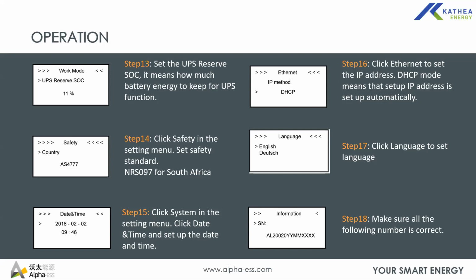On basic, you can set your language. It comes with two languages, which are English and German. It usually comes with default English, so if you feel like you want to use German, you can select German. And then there is information, which basically stipulates the system information, the serial numbers and all that, and MAC addresses. Usually you just check if your system serial number corresponds with the serial number on the outside of the inverters. It's always the same.